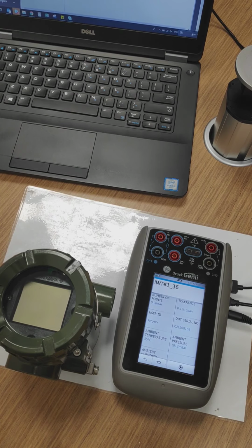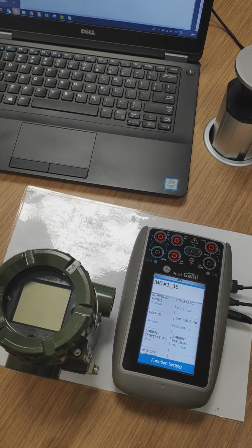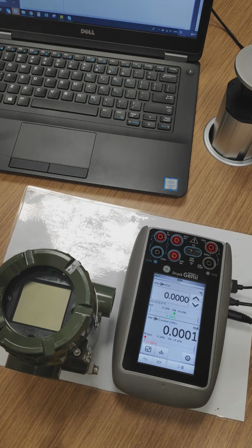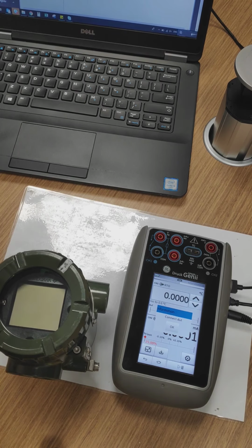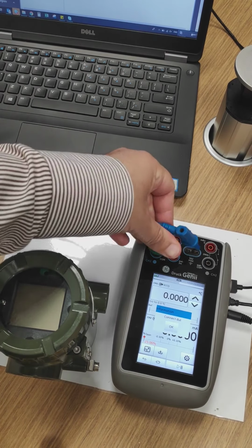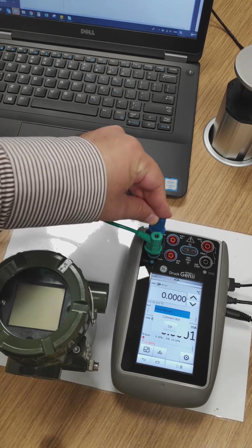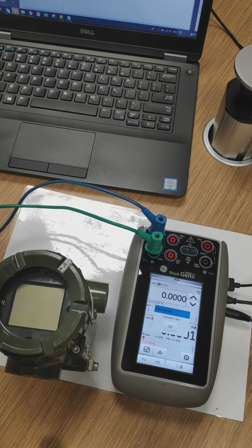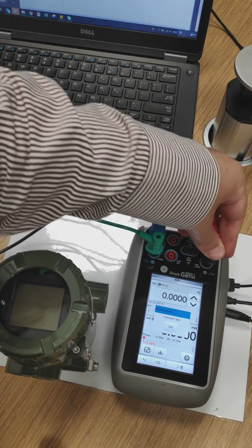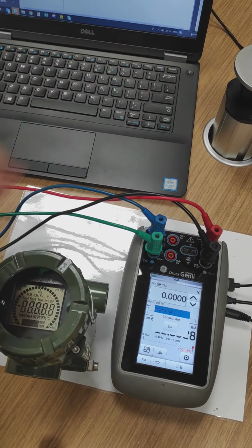Then start again. Okay. Now it is loading. Good. It will set up the channels automatically. Connect device under test. So now I need to connect the inputs and outputs. So the input is RTD. I have got two test leads and connected that to the terminals in the instrument. And the output I have is a 4 to 20 milliamp, which will be connected on channel 2. So here we go, I'm done.